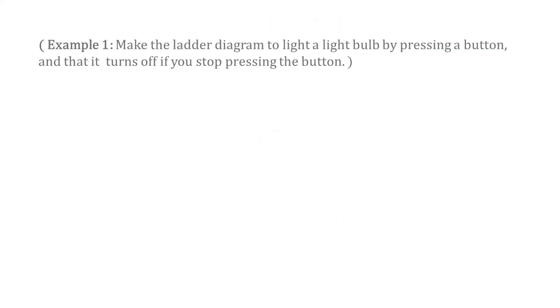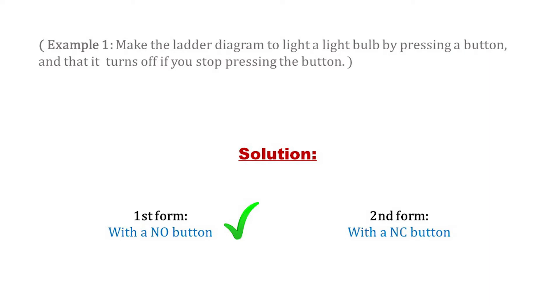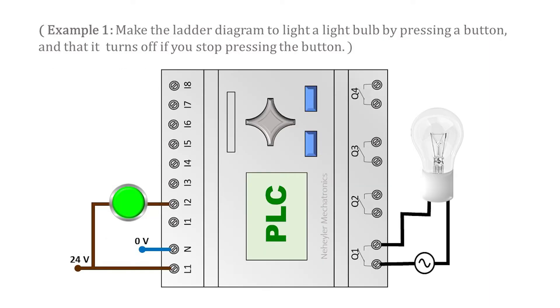Example 1: make the ladder diagram to turn on a light bulb when you press a button, and turn it off if you stop pressing the button. The ladder diagram could be made in several ways depending on how the physical inputs are considered. If the button is considered as normally open: the normally open button is connected on one side to 24 volts and on the other to the PLC input I2. The bulb is connected to the Q1 output of the PLC. The Q1 output only acts as an electrical switch, similar to a relay, opening or closing the bulb circuit.